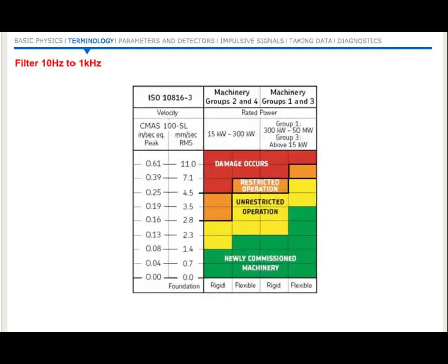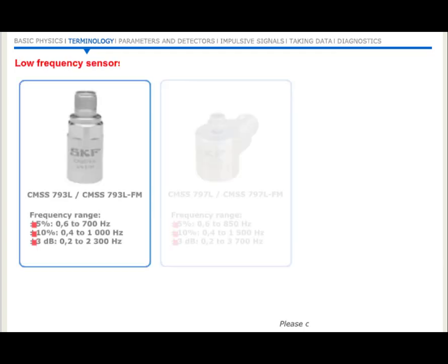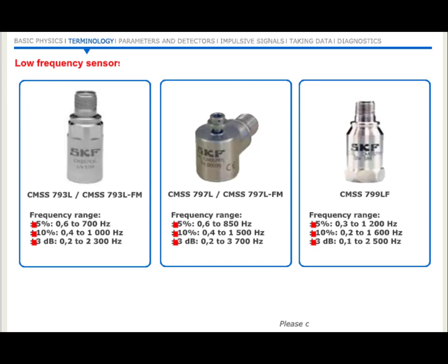The ISO committees responsible for compiling machinery vibration standards are obviously aware of this issue, and most specify that readings below 10 Hz should be disregarded. Be aware, though, that some standards specify 2 Hz. The electronics of most modern vibration instruments therefore typically offer appropriate switchable filters. To study real low-frequency vibration, it is necessary to use a special accelerometer which is designed for the purpose and which does not emit ICP noise at low frequency, for example SKF sensors shown here.